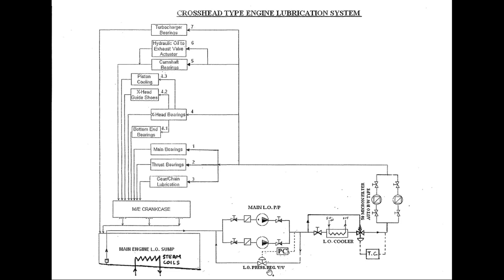The lube oil pump takes suction from the lube oil sump tank. There are two types of sumps: wet sump and dry sump. Two-stroke main engines generally have a dry sump, which is a separate tank outside the engine. A wet sump is where the oil sits below the piston in the under-piston space, as seen in generator engines with splash lubrication.